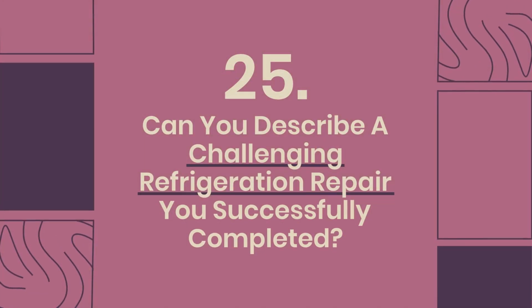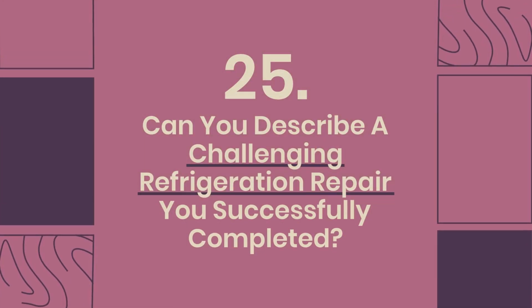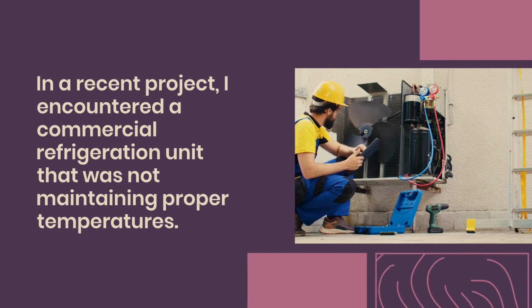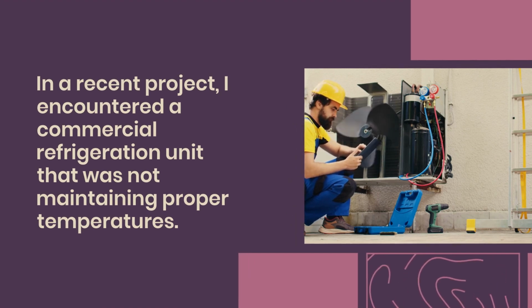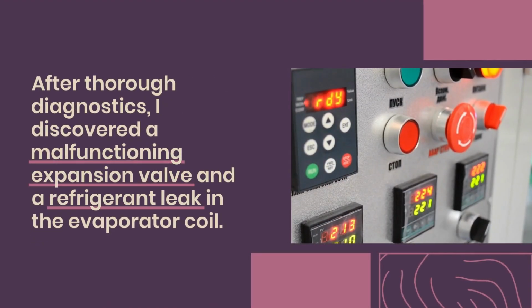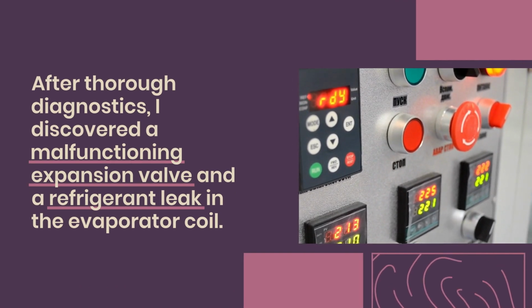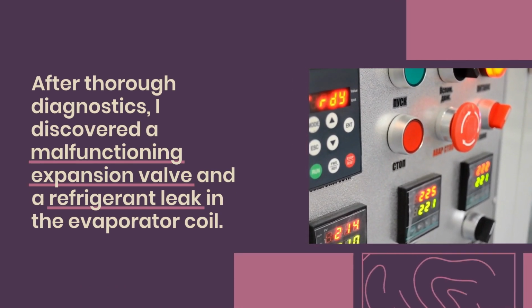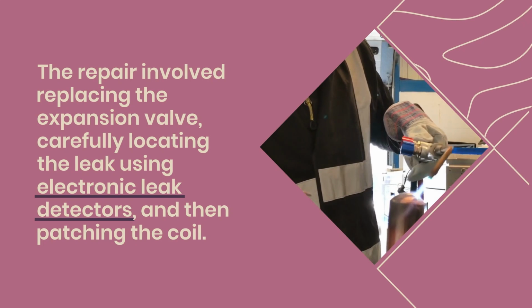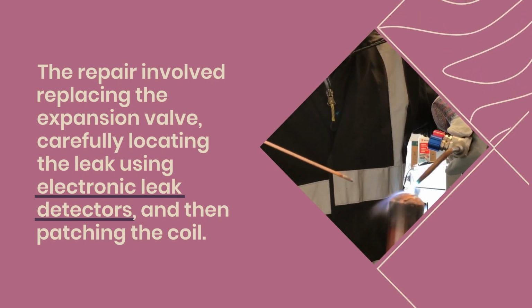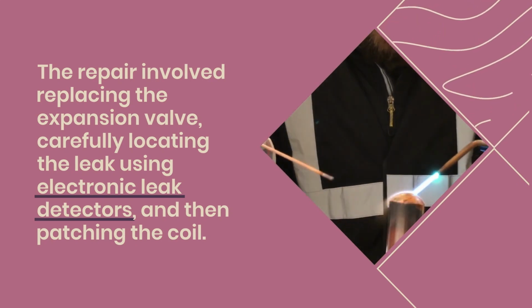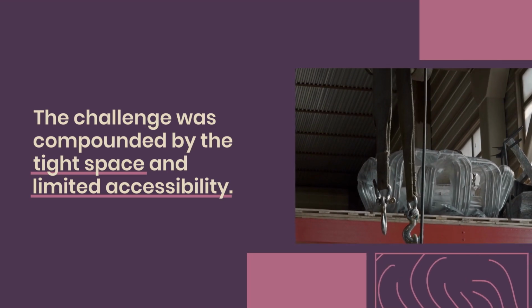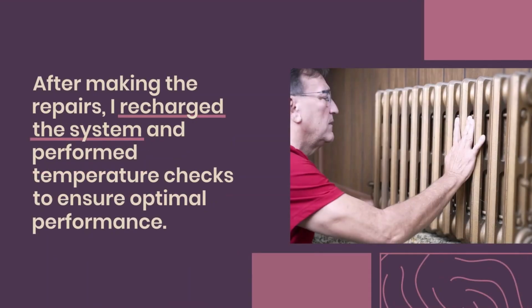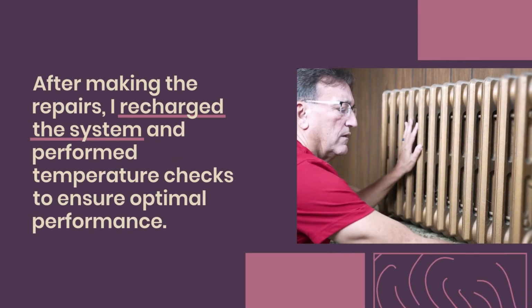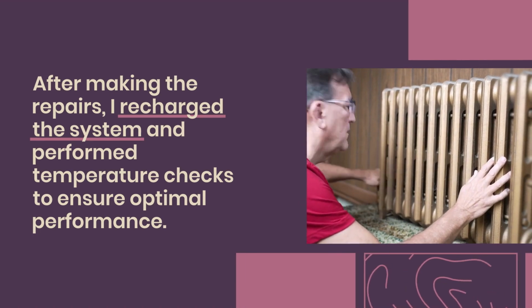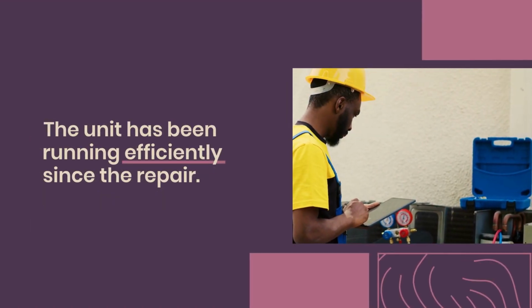25. Can you describe a challenging refrigeration repair you successfully completed? In a recent project, I encountered a commercial refrigeration unit that was not maintaining proper temperatures. After thorough diagnostics, I discovered a malfunctioning expansion valve and a refrigerant leak in the evaporator coil. The repair involved replacing the expansion valve, carefully locating the leak using electronic leak detectors, and then patching the coil. The challenge was compounded by the tight space and limited accessibility. After making the repairs, I recharged the system and performed temperature checks to ensure optimal performance. The unit has been running efficiently since the repair.